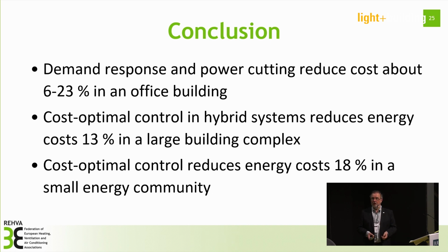Another thing is that quite commonly now all the big buildings in Nordic conditions combine two different systems, like district heating and heat pumps. We have ground source heat pump, outdoor air water heat pump, and exhaust air heat pump together with district heating, and it makes sense to optimize the use of the system based on the energy price. Based on the analysis of this large building complex, we can easily reach over 10% cost saving by optimizing when and how much we use either heat pump or district heating. For small energy communities with different energy sources and waste heat, the cost saving potential is even larger. We can say that we easily reach around 20% saving for small communities by optimizing only the use of the system based on the prices.